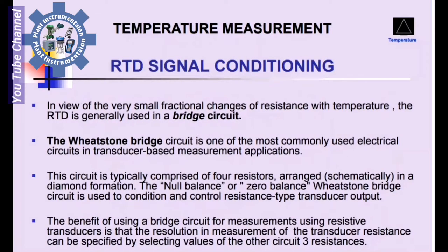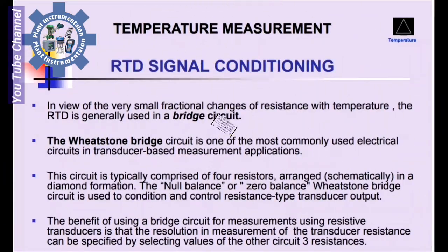RTD Signal Conditioning: In view of the very small fractional changes of resistance with temperature, the RTD is generally used in a bridge circuit. The Wheatstone bridge circuit is one of the most commonly used electrical circuits in transducer-based measurement applications. The bridge typically comprises four resistors arranged schematically in a diamond formation. The null balance or zero-balance Wheatstone bridge circuit is used to condition and control resistance-type transducers.